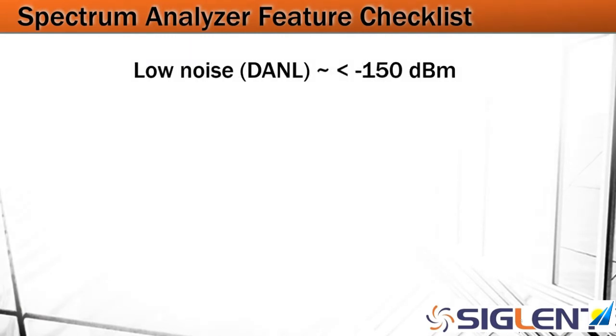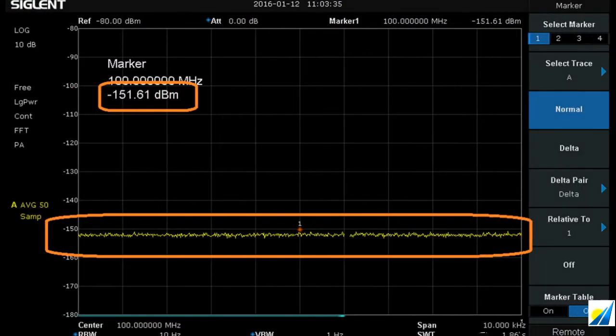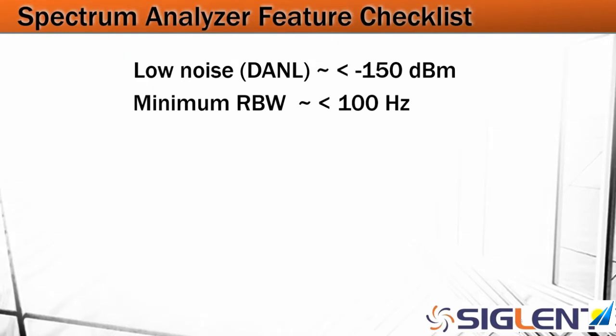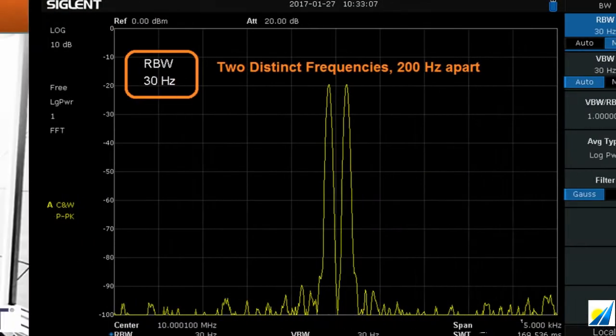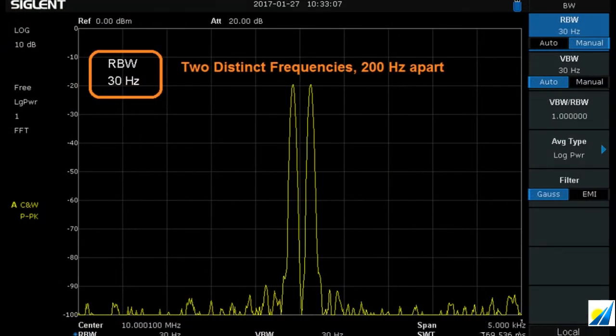Here's a quick checklist of spectrum analyzer features that may be helpful as you search for your instrument. You're going to want to look for a low noise floor or DANL — that's displayed average noise level. If you're in the minus 150 dBm range, that's going to be helpful for finding very small spurs and harmonics. Also look for a minimum resolution bandwidth of around 100 Hz or less.